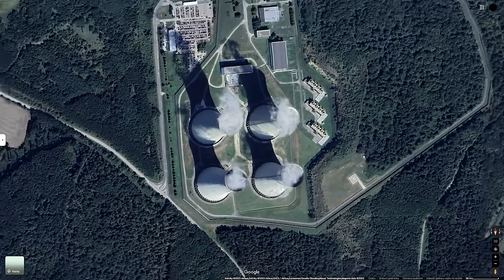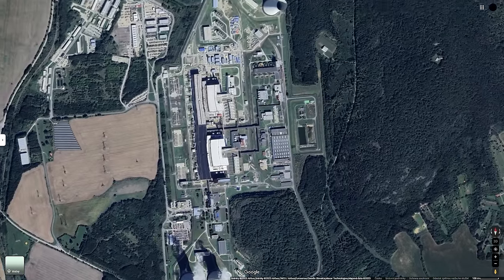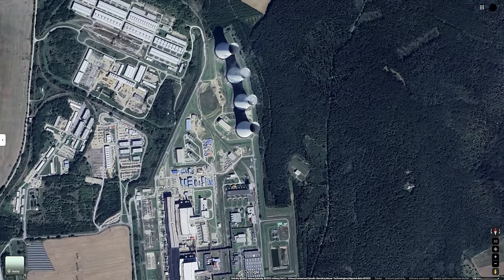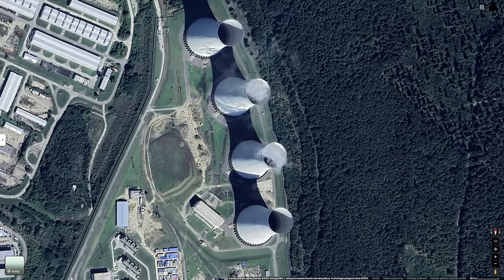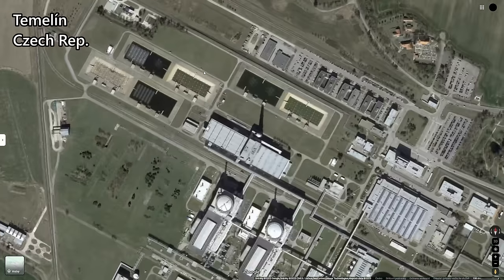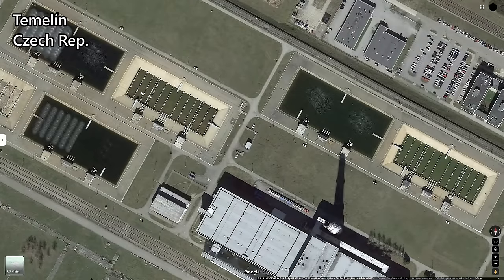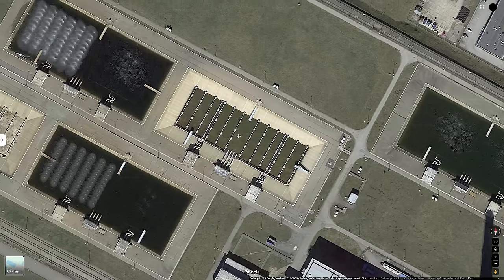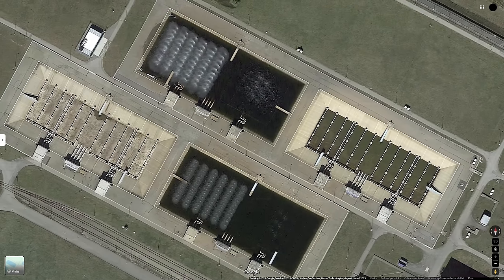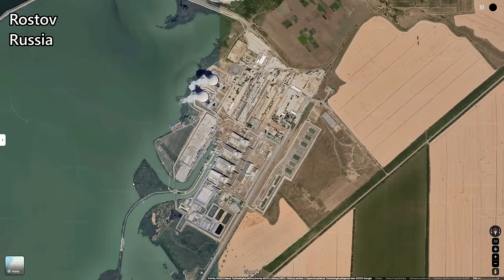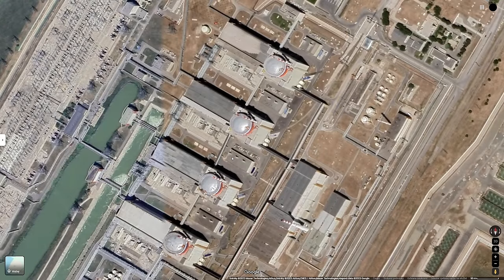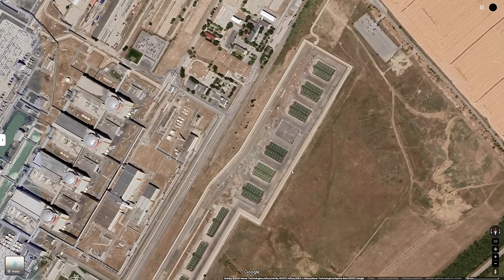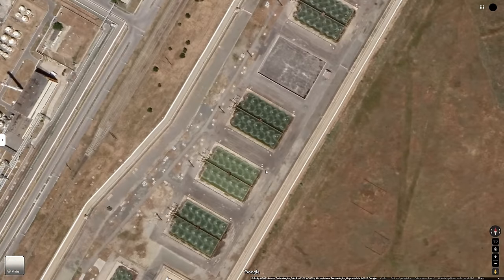If you cannot dump the hot water, then you must cool it on site using cooling towers. Every single power plant here has two cooling towers per reactor, no exceptions. The VVER 1000 reactors also require spray ponds, fairly small ponds with pipes that spray water into the air so the droplets cool down and fall into the pond. I'm not quite sure why this reactor type needs them, but every single one has them, alongside other cooling options.